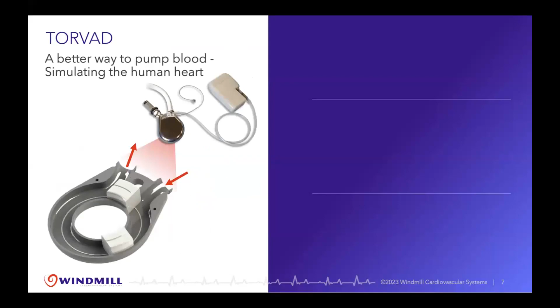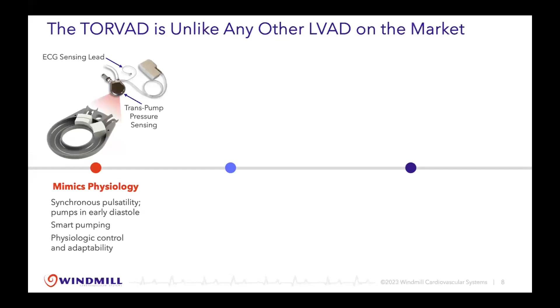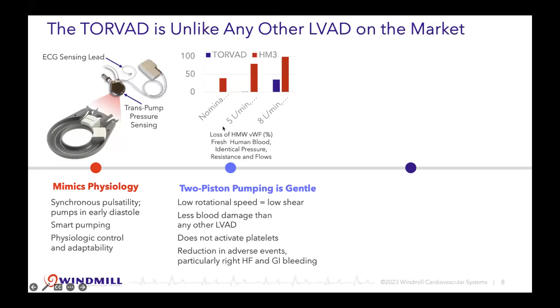So one thing that he didn't mention was we have an EKG lead that we suture to the surface of the heart, which transmits the electrical impulses from the heart to the pump and allows the pump to make decisions on when to pump and how much to pump and so forth. And in addition, it has the ability to measure the transpump pressure, which also allows it to detect low blood pressure or high blood pressure and adjust the pump's function based on those inputs. And at the present time, no one has anything like that. He's already gone over the blood trauma, which is far better with the TORVAD than with the HeartMate 3.